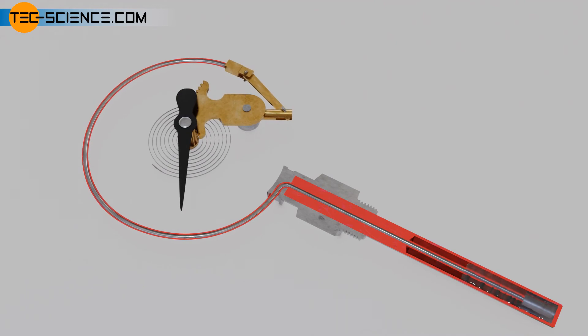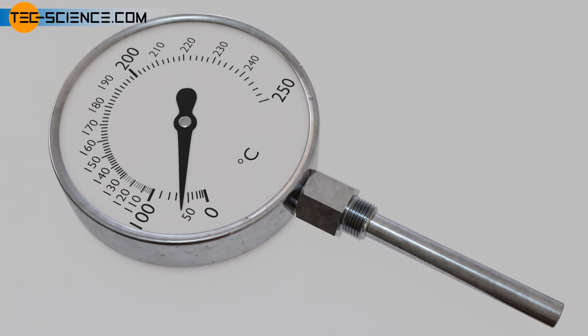Since vapor pressure curves are not linear, the scale of vapor pressure thermometers is not divided into equal steps. Due to the exponentially increasing vapor pressure curves, the scale distances increase with higher temperature, so that the measurement sensitivity and accuracy increases as a result. Vapor pressure thermometers should therefore be used in the upper third of the scale for sufficient measurement accuracy.